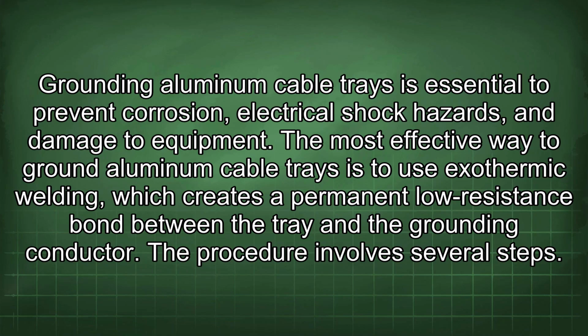Grounding aluminum cable trays is essential to prevent corrosion, electrical shock hazards, and damage to equipment. The most effective way to ground aluminum cable trays is to use exothermic welding, which creates a permanent low-resistance bond between the tray and the grounding conductor. The procedure involves several steps.